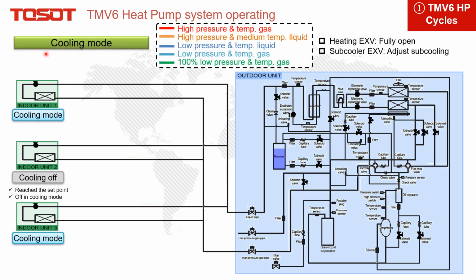So let's say it is in cooling mode, and I also show the status of the refrigerant, either high or low pressure, and either gas or liquid. Let's say these two indoor units are calling for cooling. And this one, I make it cooling off, meaning it reached the set point, or it is already turned off in standby mode.